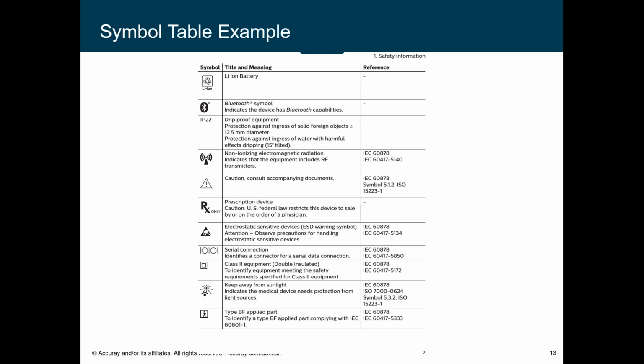Because if you're saying just ISO 15223 and this symbol changes, then you're out of compliance. But in my opinion, if you have 15223:2016 and this symbol changes in the 2020 version, then you're still, quote unquote, in compliance because you're referencing the correct version, and it gives you a little bit of buffer time to be able to update that symbol when you have the time. The other piece to remember is to be sure that these symbols reflect back to your product label, and being sure that you're using consistent product labeling symbols.